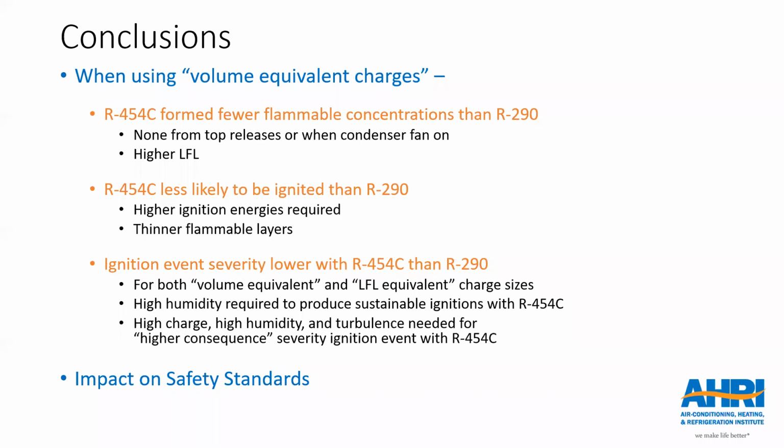We also found that you needed high humidity to produce a sustainable ignition with 454C, one that would keep going after the igniters were turned off. And you needed the combination of high charge, high humidity, and turbulence to produce a higher consequence ignition event with R454C. So this study was completed last year. The report has been published and is available on the AHRI website. And the findings have been shared with groups working on the development of safety standards, such as the IEC and CANENA Working Group 12, working on the international and national versions of the 60335-2-89 standard.